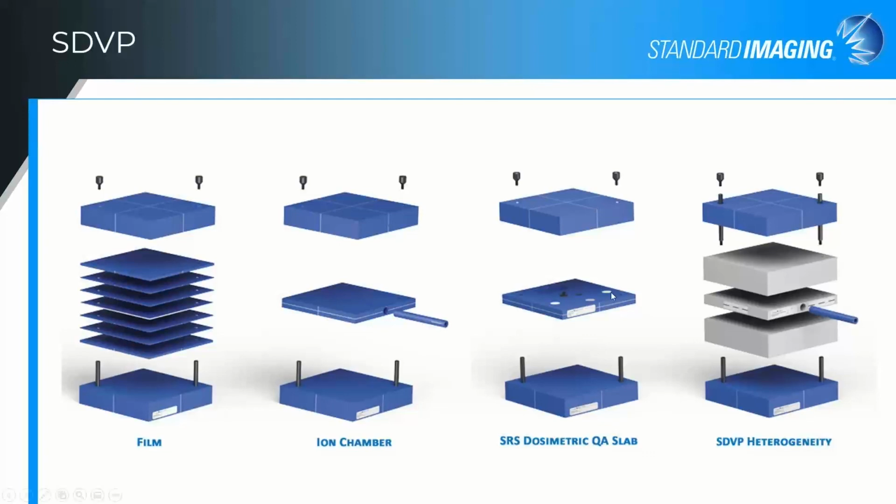So this is an excellent way to commission or validate your SBRT calculations with your TPS, and in fact was designed for the Monte Carlo commissioning with the CyberKnife in order to validate that it was really performing the calculations as expected as you're getting your system commissioned.